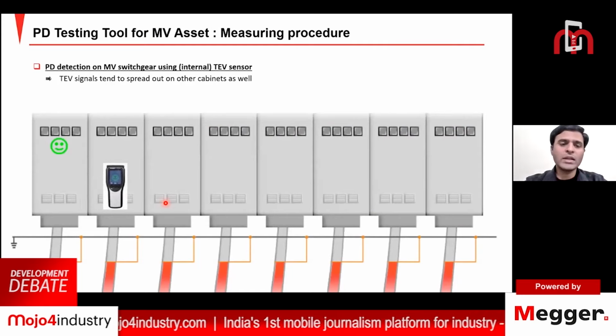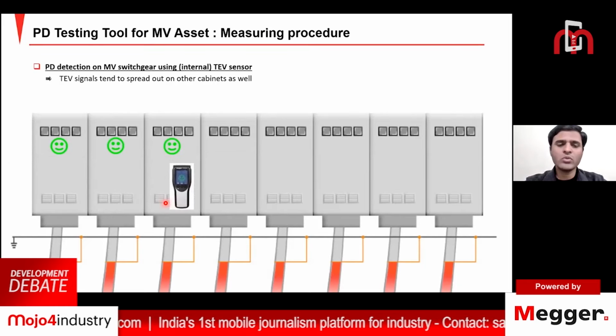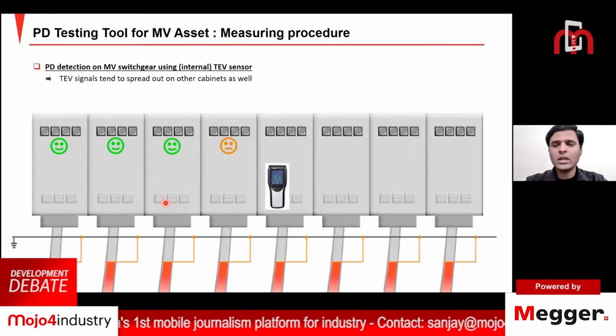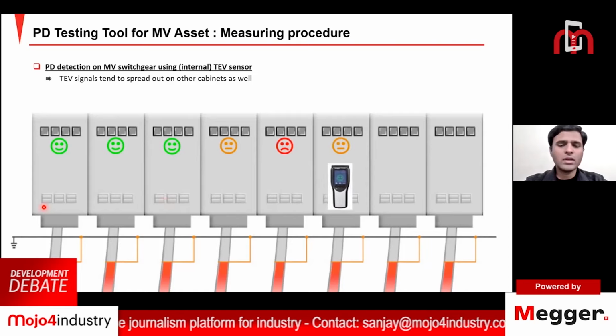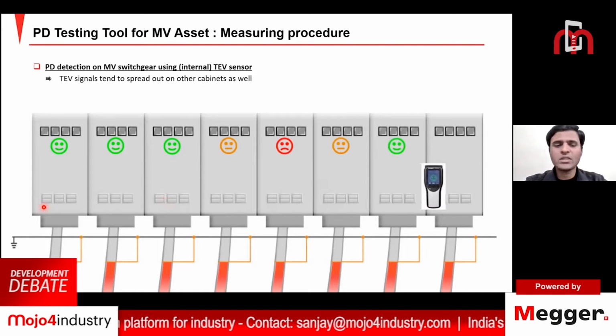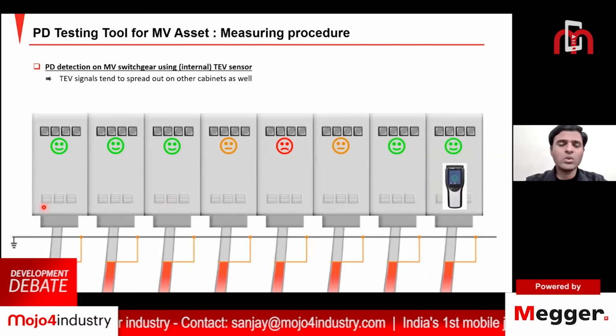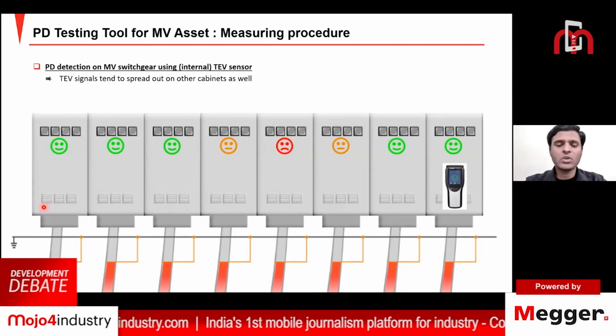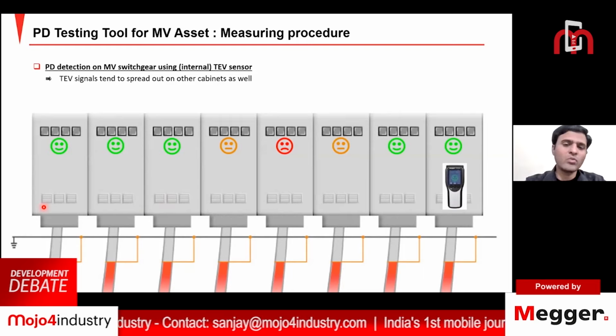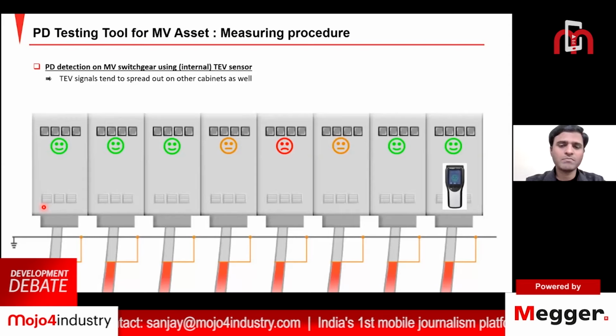Some of you may think, is there any threshold value for partial discharges? Up till now, there are no standards, but we can carry out condition based maintenance on that particular asset. If you have a number of panels, you can measure on all the panels and maintain a threshold level for the PD activity, and you can carry out regular monitoring on the assets. So using a TEV sensor on the medium voltage switchgear panels, you can very easily identify the particular switchgear panel which is generating or emitting the PDs.